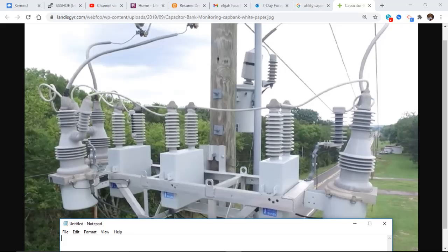Now let's say it's spring and none of the air conditioning is running, and we really don't have that much motor load out there close to the college or in the college. Do we want this thing to be running? No, go the opposite direction. Now, do you think that every day a lineman's going to be running back and forth to this capacitor bank and turning it on and off? No. What do you think controls it?